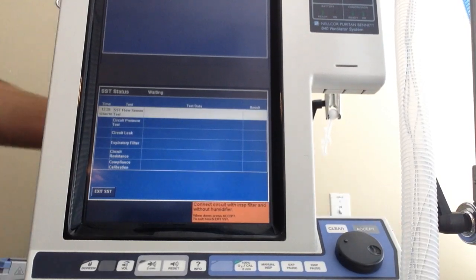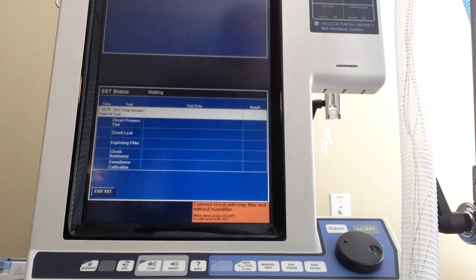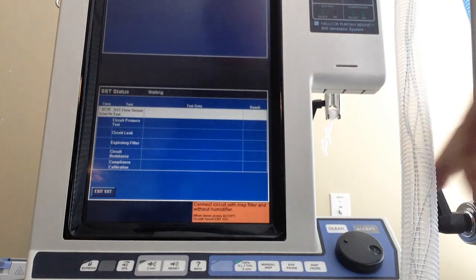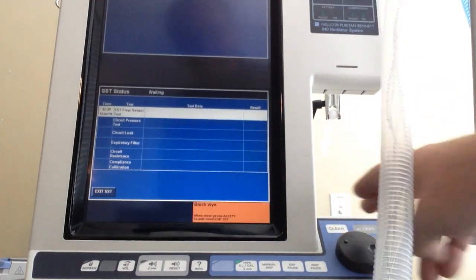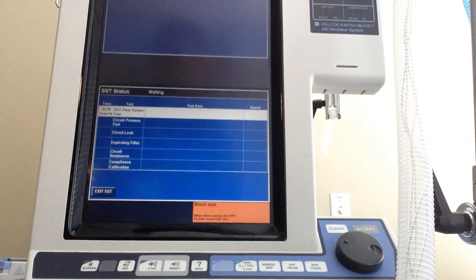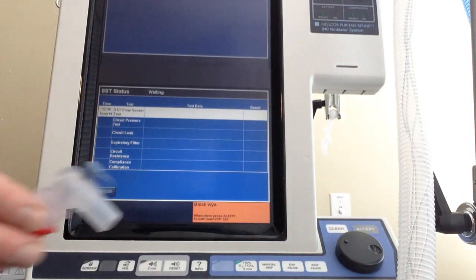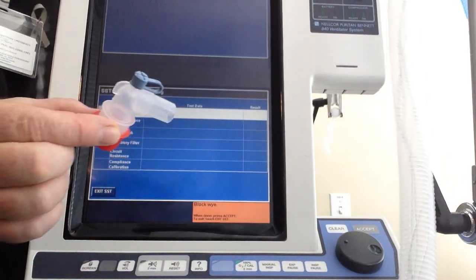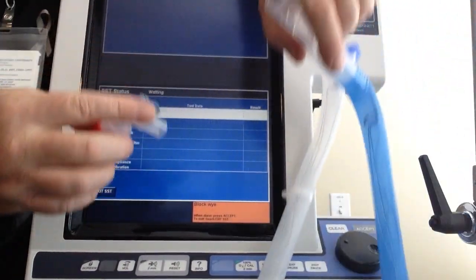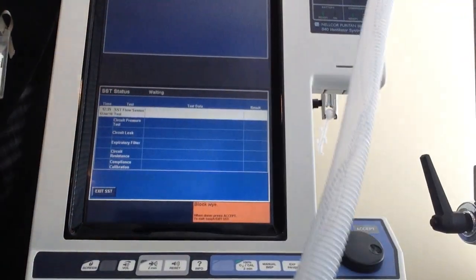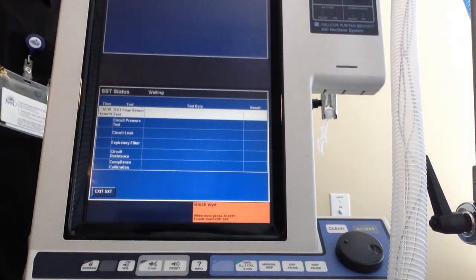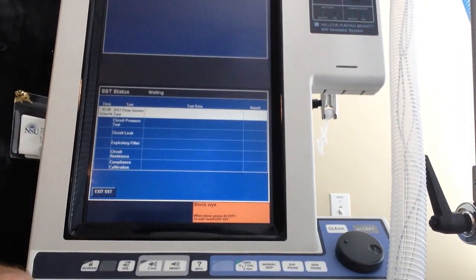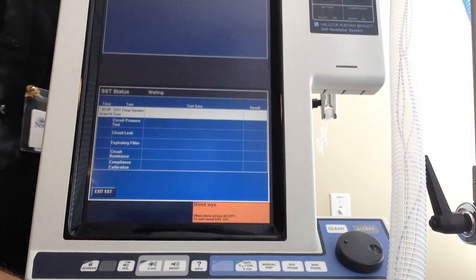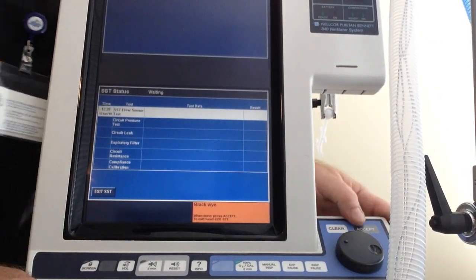Please wait. And then you practically read the directions on the front. Connect the circuit with inspiratory filter and without humidifier. I did that. Block the Y. I'm going to retake my cap and reblock my Y. Now, whenever you're doing these pre-use tests, do not hook it to a humidifier. You will not pass the test. These humidifiers will leak because you're not plugged up to water. Once I block my Y, I hit accept.